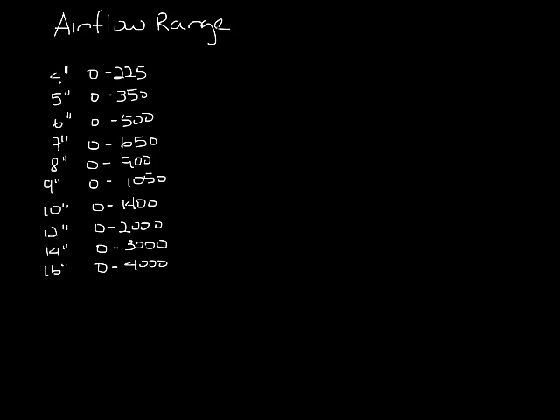So let's talk about the low end first. Zero is obviously a closed damper, but can you really put 1 CFM through a 10-inch inlet? Well, yeah, probably you can, but you won't be able to measure it.